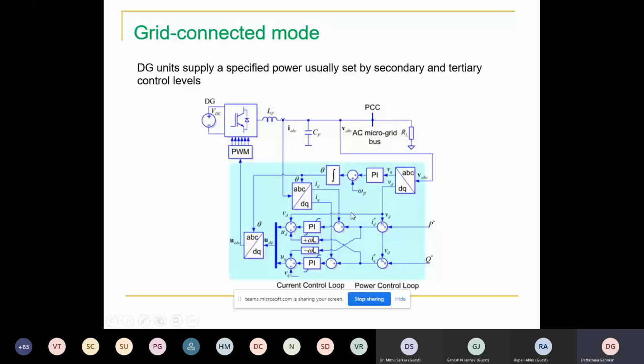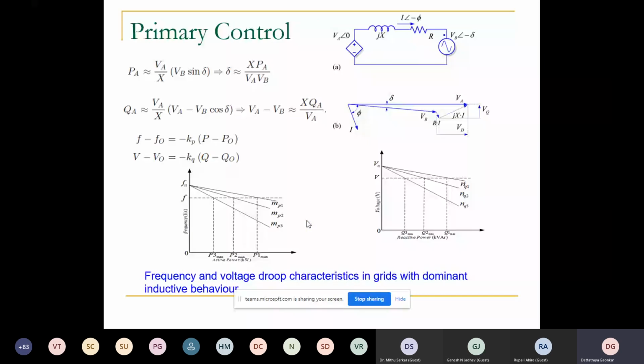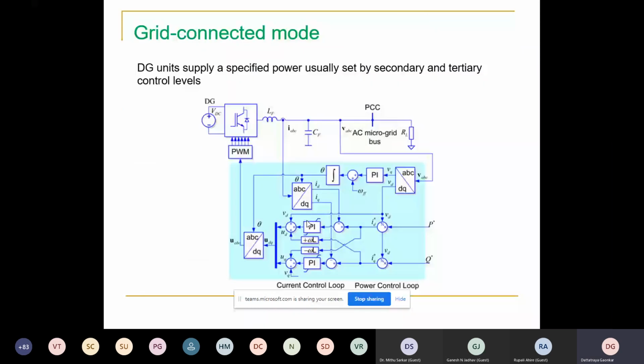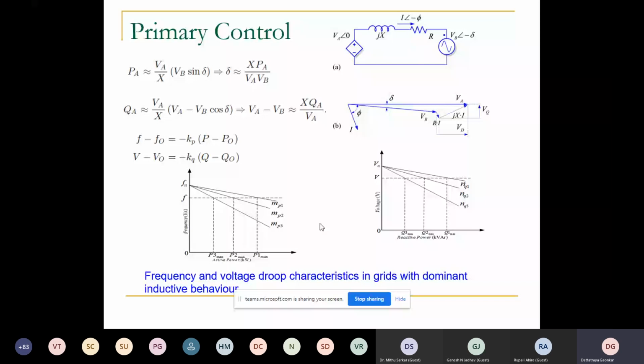You can think of voltage and frequency as having become standard. Now, imagine this with a single inverter. If you have multiple inverters with a common load, who will tell them how to share? A synchronous generator has natural droop characteristics, which are not there in a power electronic interface. You have to introduce droop externally. You know the droop characteristic, frequency and voltage droop. You have to introduce a droop so that they share the loads.